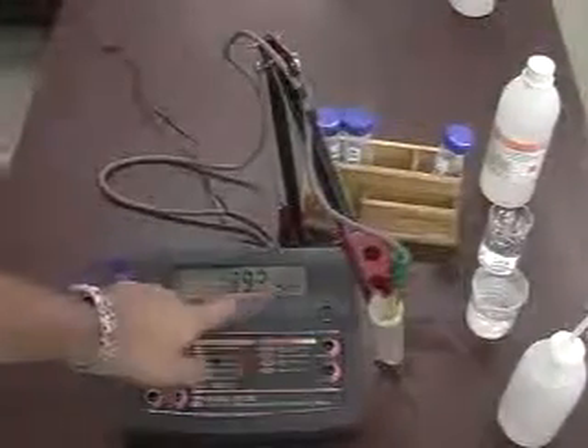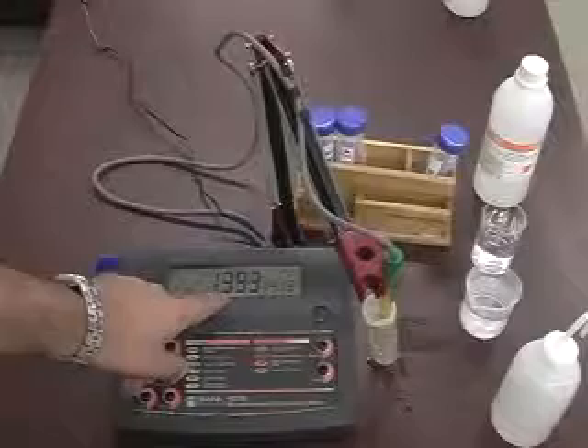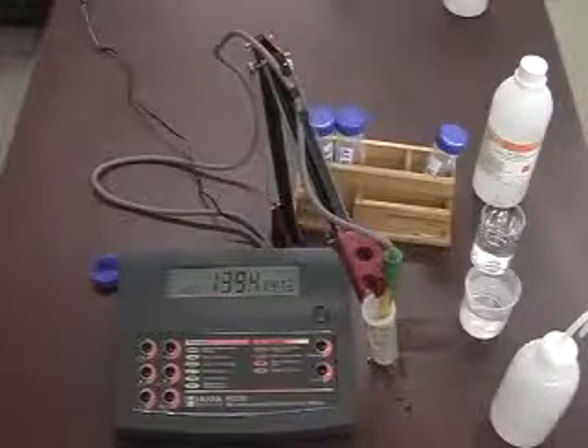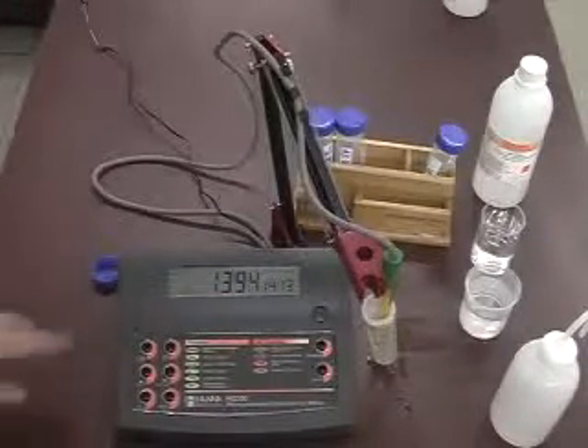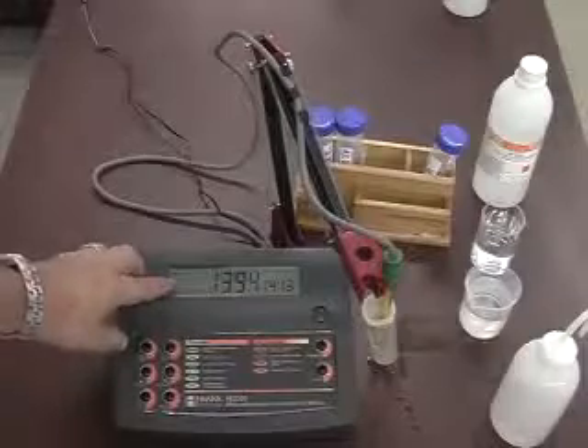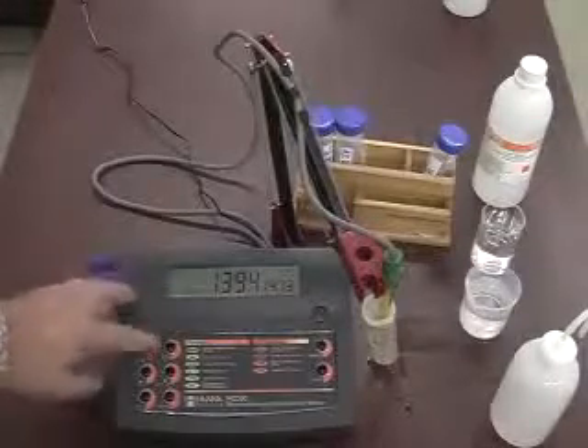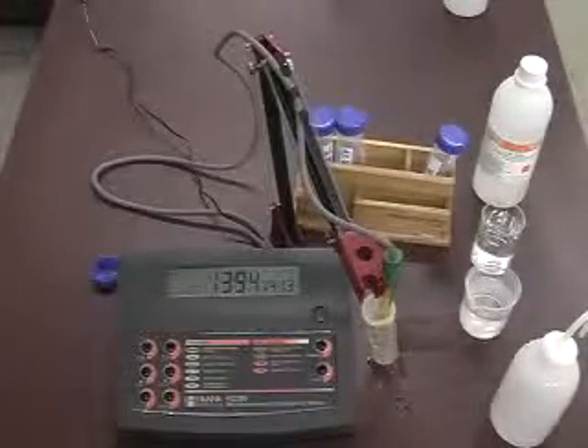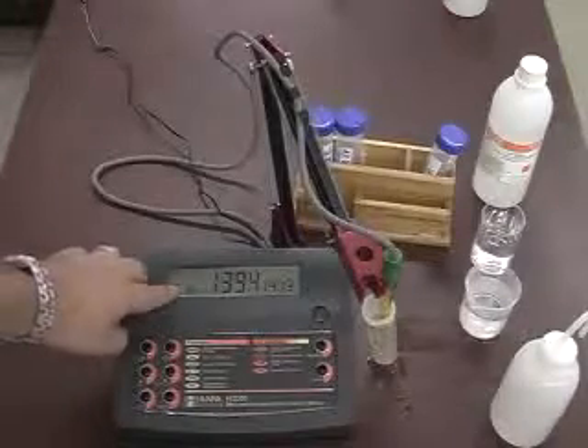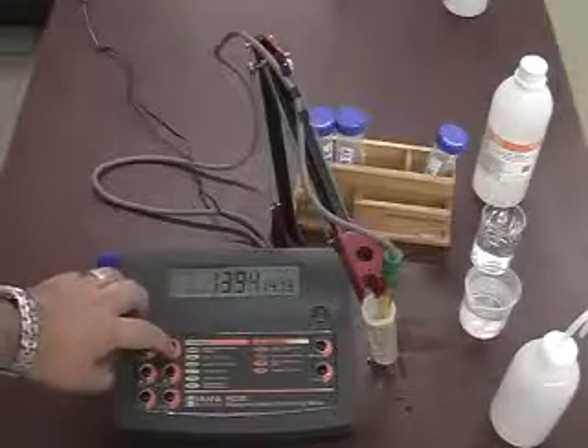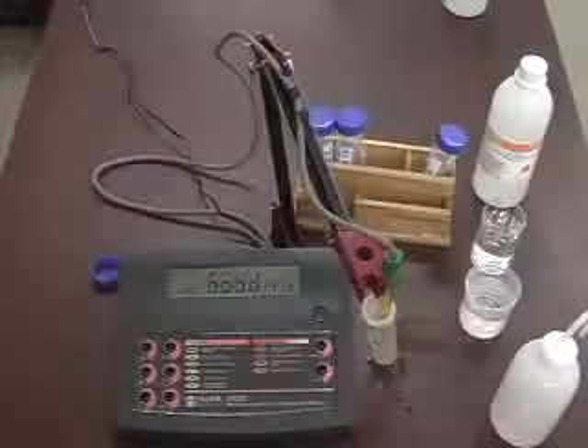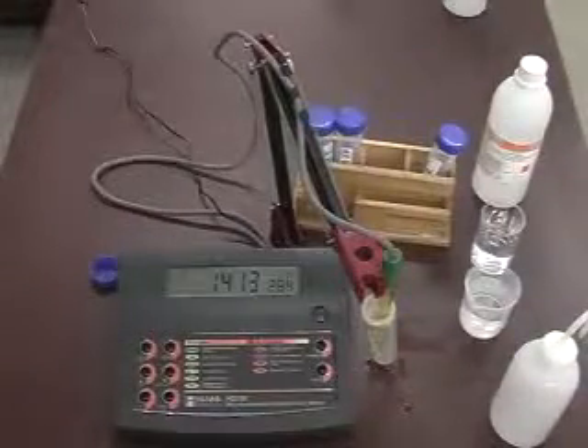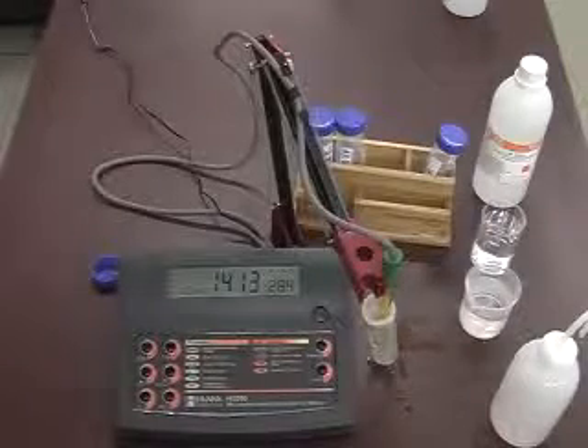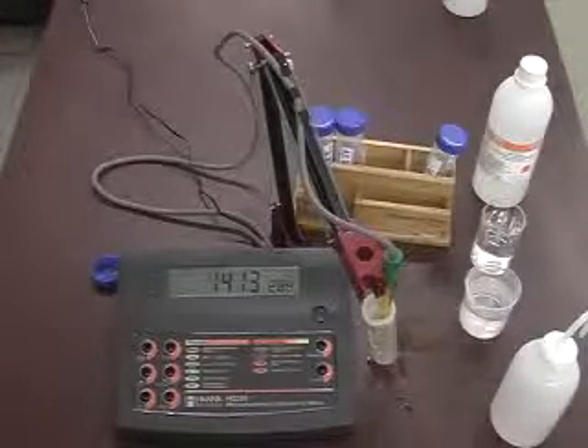It is prompting for the 1413 microsiemens solution since it knows it's going to be close to that value. Once it stabilizes and it recognizes that value, CFM will show on the display. At that time, we will hit the CFM button to confirm that value. So right now it's flashing CFM. I hit confirm. It tells me the calibration is good, it's accepted within a certain tolerance, and now the meter is calibrated using the 1413 solution.